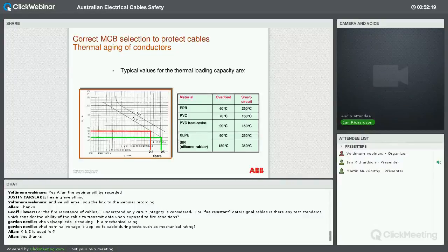Now, it's a little bit unrealistic to say that this is actually going to happen. You're not going to operate that cable at a temperature 20 degrees above its rating continuously for that amount of time. But what the graph is actually highlighting is that allowing a cable to operate at a higher temperature can have a very severe impact on the life that you would expect out of that cable. Your insulation will deteriorate, and it's mainly because you're using the cable outside of its designed capacity, its designed rating. So it's very, very important that we consider our circuit protection to allow the cables to perform at their best for their longest.